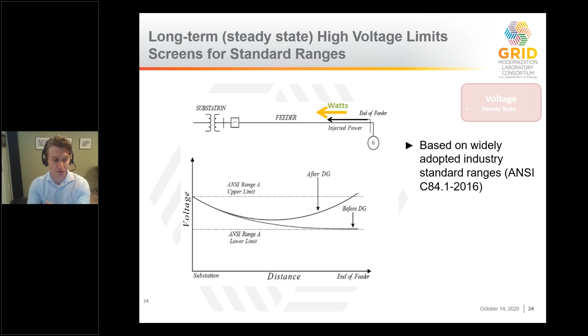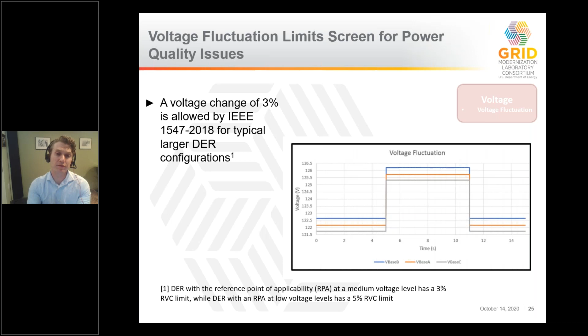Another voltage related issue is looking for the voltage change from a DER unit being on to a DER unit being off. It's sometimes called voltage fluctuation, and there are a couple of components, but the one that is most relevant here is a rapid voltage change limit. If there's an abrupt change in the output, and there are a number of factors that can cause that, not so much cloud cover but something that's an even faster event, there can be a step change in voltage, and that can cause equipment problems. Next slide, please.